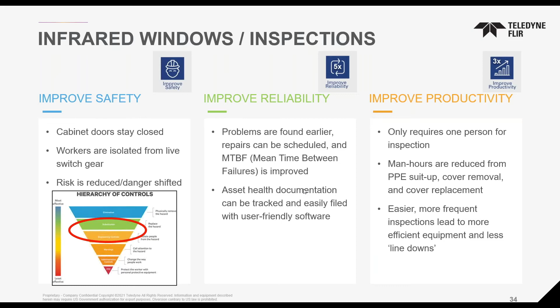Here are a couple of images. On the left, you can see with IR windows we're able to do both thermal and visual inspections. The gentleman in the two images on the left has minimal PPE—just his hat and safety glasses—because the cabinet door is left closed. He doesn't have to wear the NFPA rated PPE suit for arc flash that we see on the right when they're actually opening up these doors, which brings a lot more danger to that person and that facility.